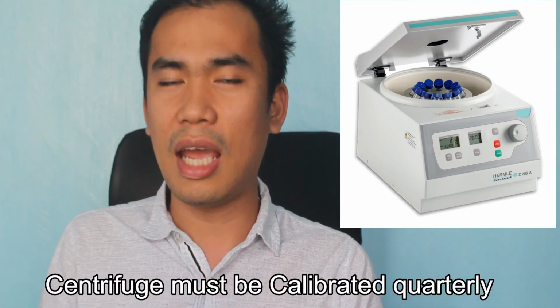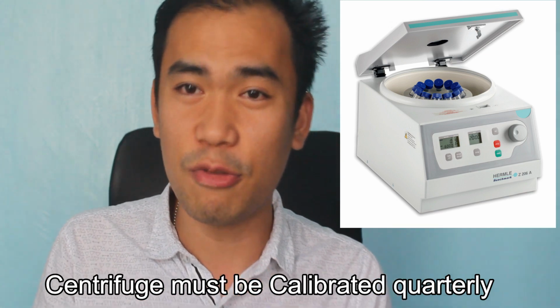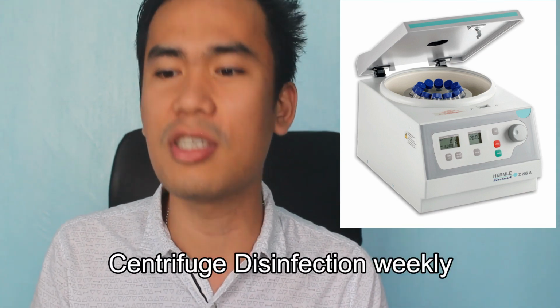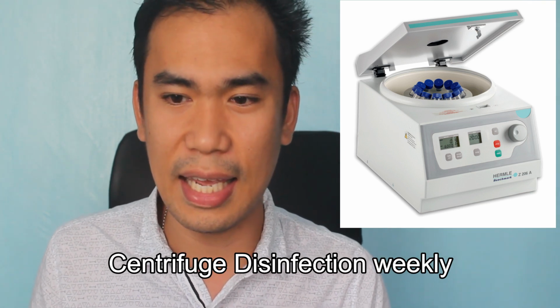Okay? So, let's go back to centrifuge. Kasi palaging lumalabas. The question is, how often do we calibrate the centrifuge? The answer is quarterly. Okay, so how often do we disinfect the centrifuge? The answer is weekly.